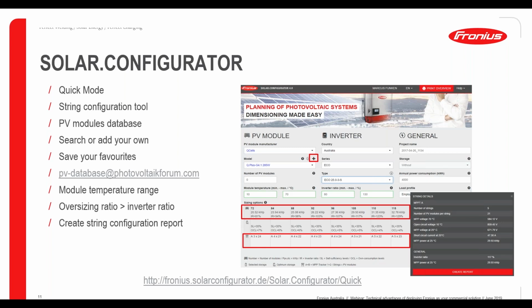But effectively, within the module temperature min and max, this will give you a lot more options for the sizing and configuring of the strings connected to the Eco than if you did run with the -10 side of things. Bearing in mind the inverter ratio, if you're going to use the solar configurator, we run between, say, 80 and 130 as the max. We do have a little buffer in there so that if you are setting up an STC sort of system, you're still within that 133% rule of the CEC.